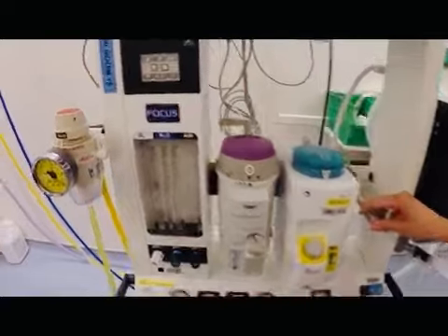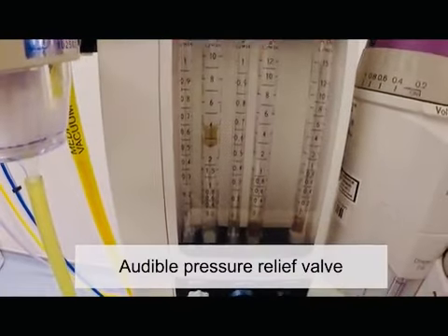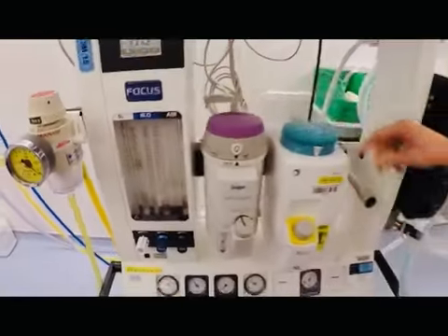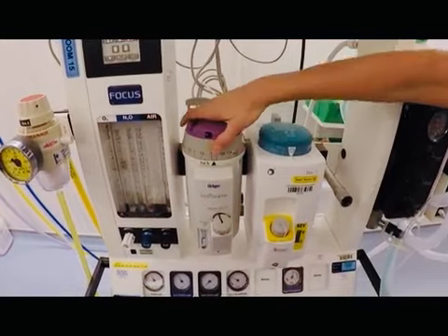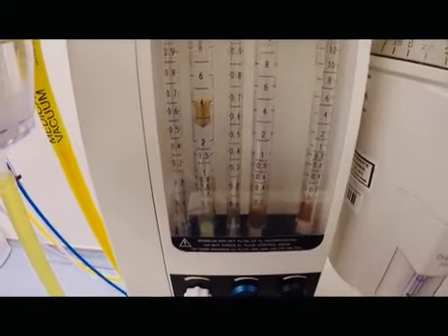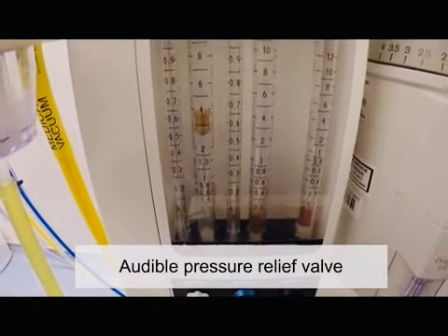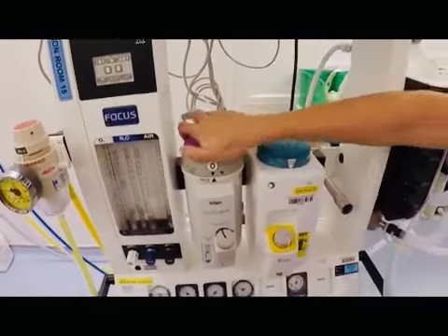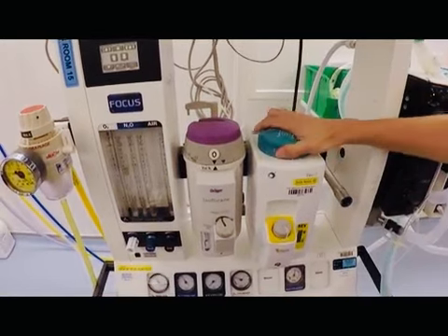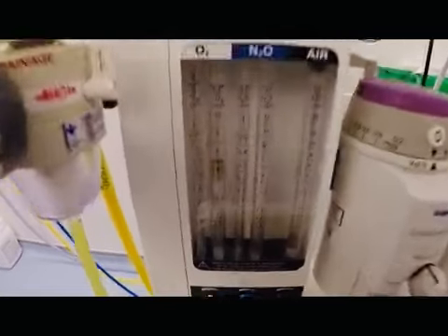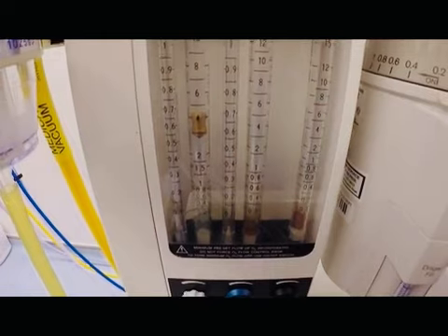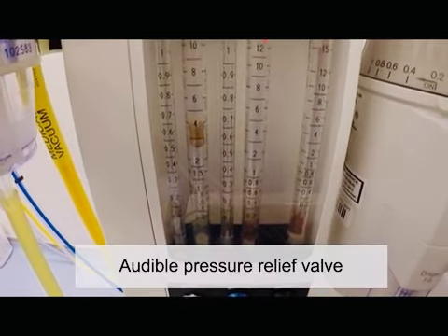The back bar and the vaporizer now need to be assessed for any leaks. This is done first by occluding the common gas outlet with the vaporizer switched off. This should cause a pressure build-up in the back bar with backflow to the flow meters so that the bobbin drops and the pressure valve on the back bar releases. Then repeat the test with each vaporizer on in turn and the same response should be elicited.